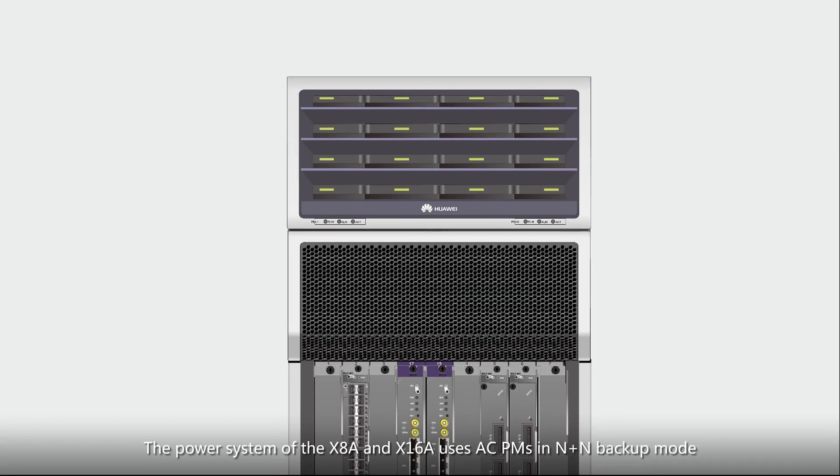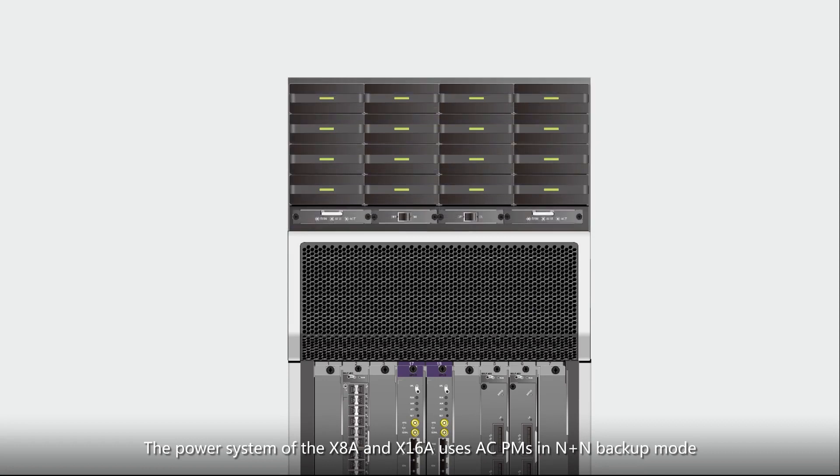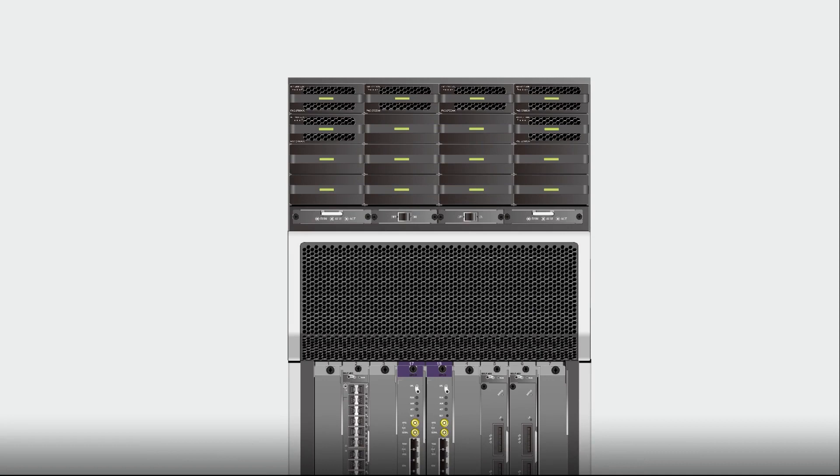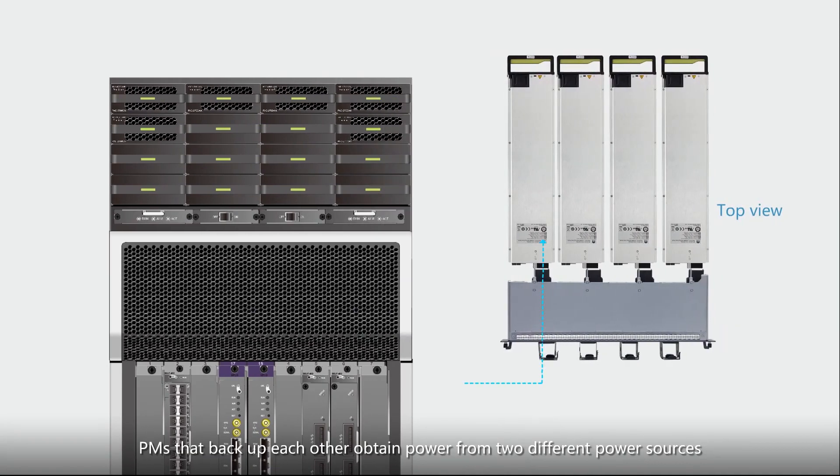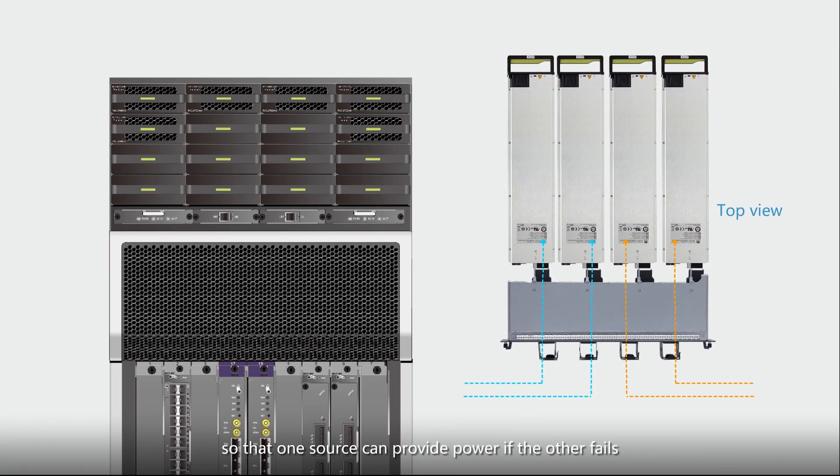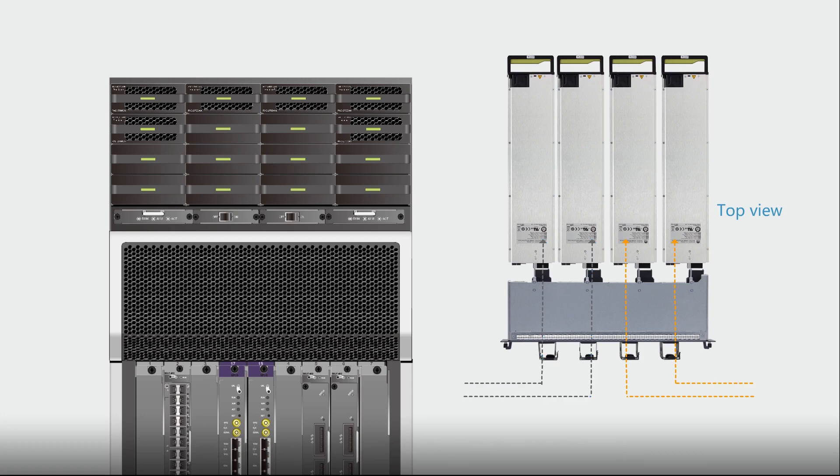The power system of the X8A and X16A uses AC PMs in N plus N backup mode. PMs that backup each other obtain power from two different power sources so that one source can provide power if the other fails.